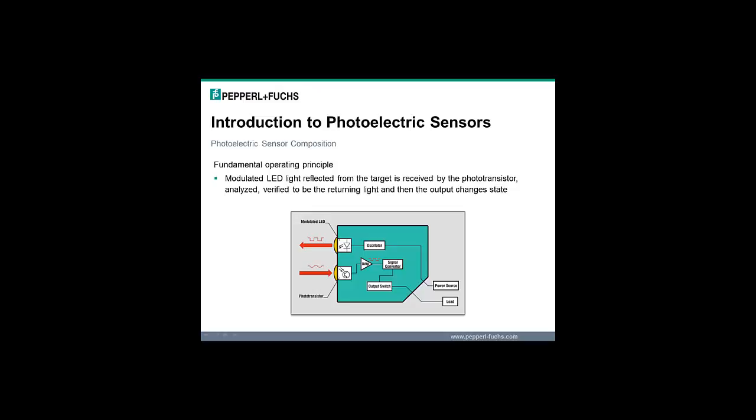A photoelectric sensor operates by emitting modulated light — that is, the light is quickly pulsed on and off, the timing being controlled by an internal clock or oscillator. The receiving element, most often a phototransistor, collects the return light and internally evaluates the amplitude. If this amplitude meets a predetermined condition, a signal is given to the output element, instructing it to switch its operating state.